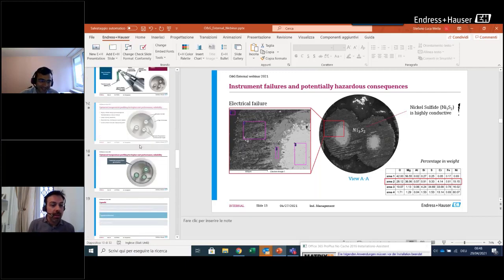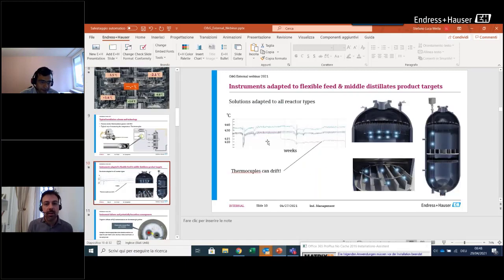What happens at the end is something like this: you will see that the thermocouple drifts, and then slightly it goes back to the normal conditions. Most of the time, customers say, okay, the thermocouple started to work again. Yes and no, it's working, but in the wrong position. So you think you are measuring here, but maybe you are measuring there. The process control is highly affected, and the efficiency of the process goes down. If it's just one point, okay, but when it comes to more than one point, the process control becomes really critical.